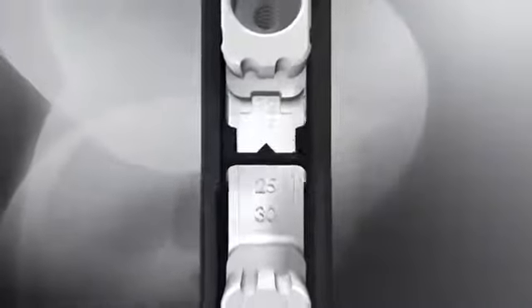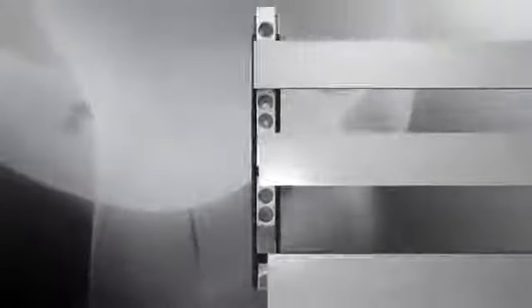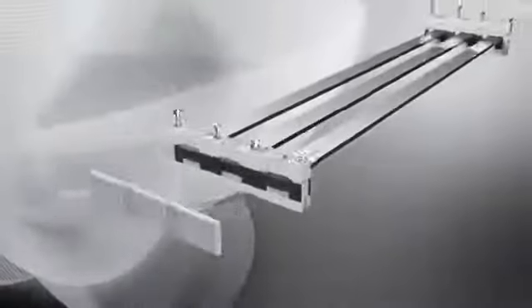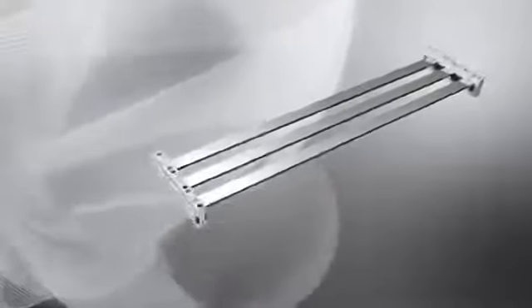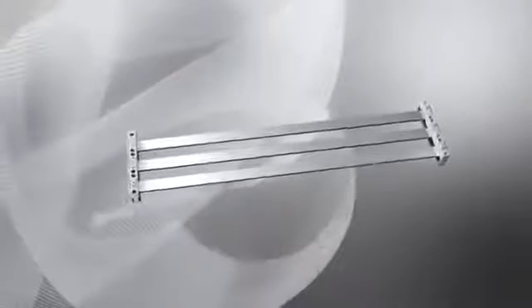For flat bus bars with a thickness of 5 and 10 millimeters, Woehner has developed a universal bus bar support that can be adjusted to various bus bar widths. The slide can be adjusted to widths of 12 to 30 millimeters. The universal bus bar support comes in 2-pole, 3-pole, and 4-pole versions.